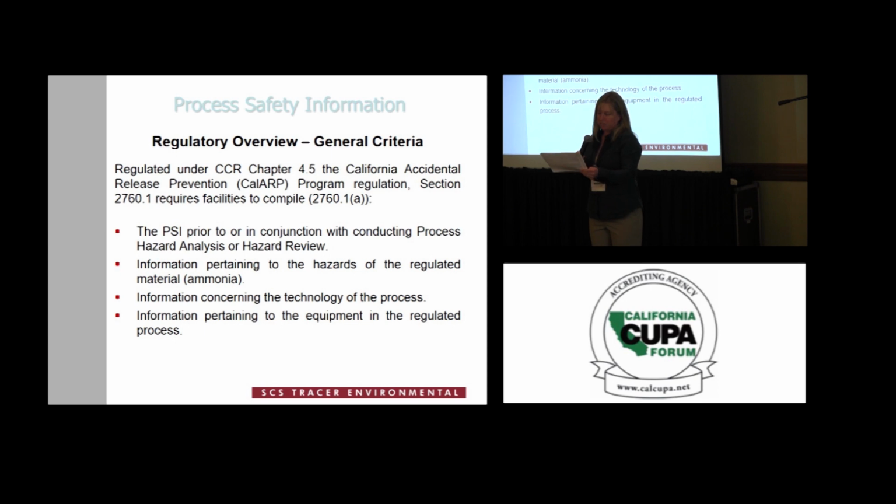Material and energy balances for process built after May 26, 1992. And that's found in the OSHA regulation. I believe if you read the RMP, it says 1999. So if they were around before 1999, then you got to default back to the OSHA criteria for having that material and energy balance. This was the energy balance. They were close. And actually, the difference is the way they run the system. I think we had to actually add an explanation in there. They were really close on their energy balance.